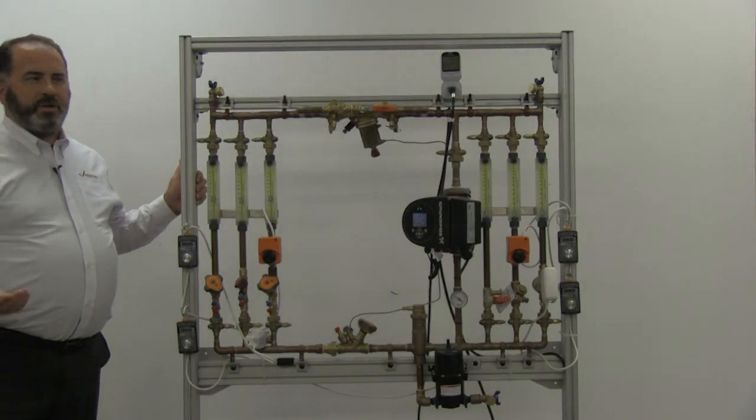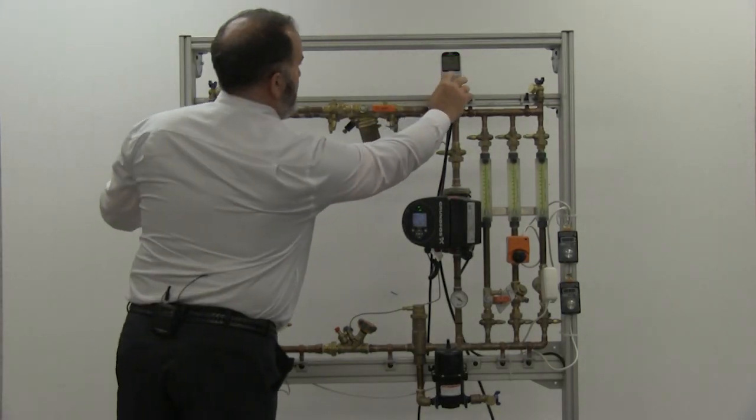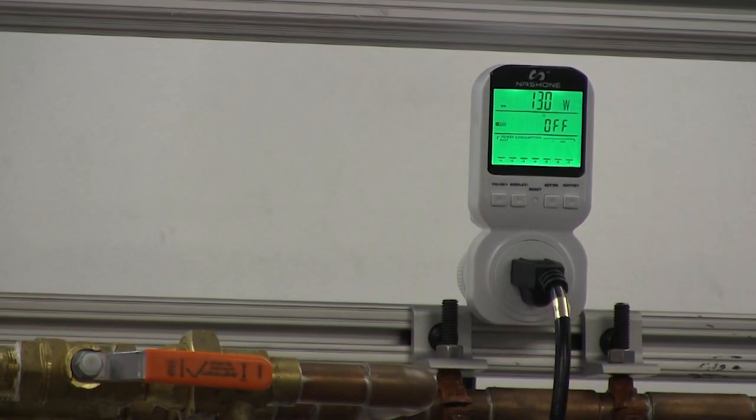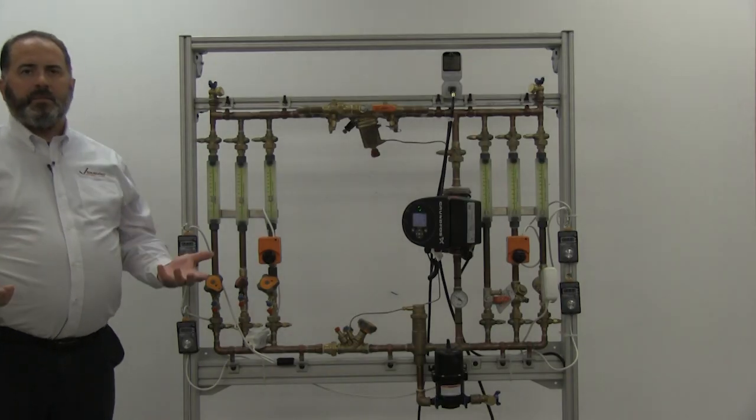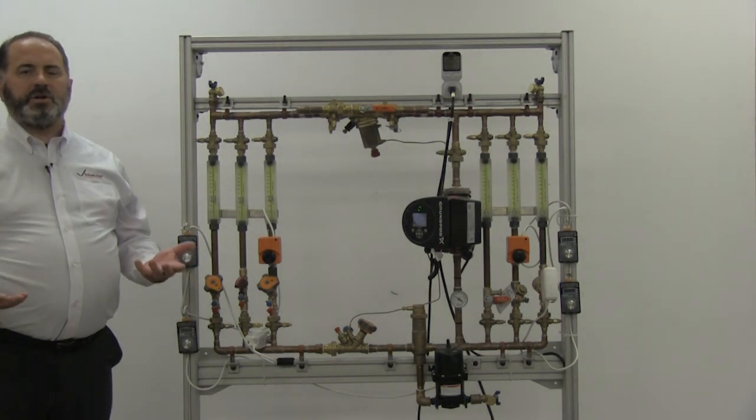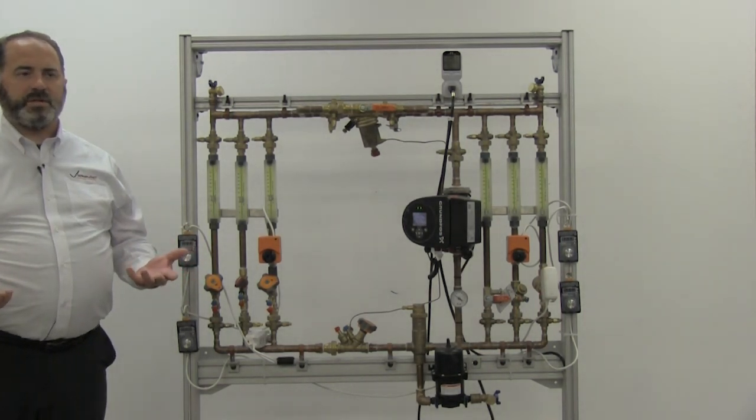What did that do to our energy usage? Look at that again. Now instead of being at 178 watts, we're now at 130 watts. So we've reduced a significant amount of energy usage just by balancing our system, by adding balancing and correctly establishing the flow rates where they need to be per design.